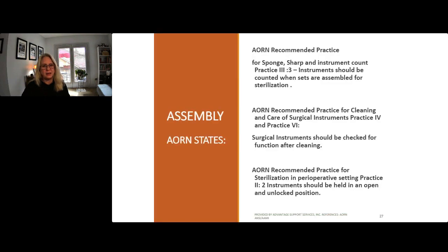AORN is stating that for sponges, sharps, and instrument counts, instruments should be counted when sets are assembled for sterilization. They're also stating in their practice of cleaning and care of surgical instrumentation that instruments should be checked for function after cleaning. So do you have the right equipment and inspection tools at every assembly table to make sure that you can inspect the instrumentation for functionality?